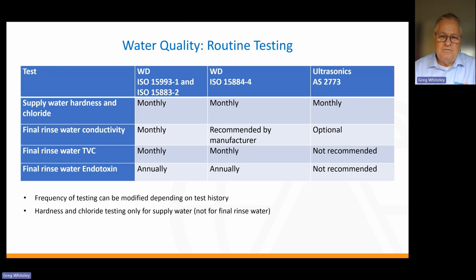Likewise, if you're covered by 15883 Part 4, there are obviously some other requirements. And if you've got an ultrasonic device for cleaning, it's about doing testing regularly, but really it's only water hardness and chloride that you need to test for, and that's got to do with the corrosivity of the water. You don't want to leave water on devices that's got a lot of salt, because you'll get pitting and corrosion.